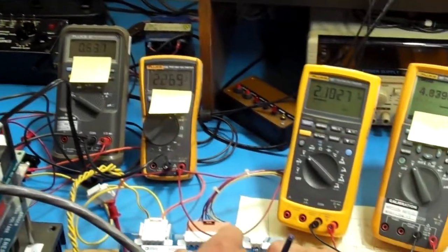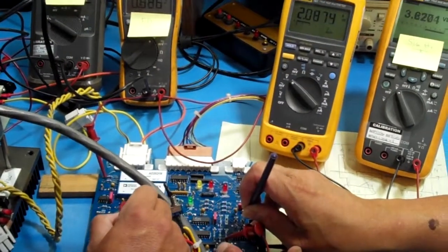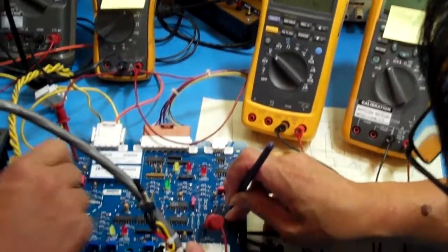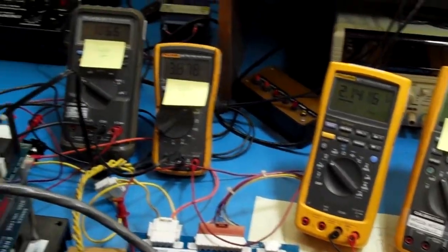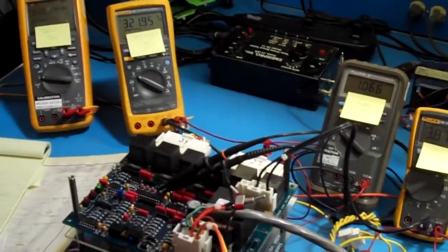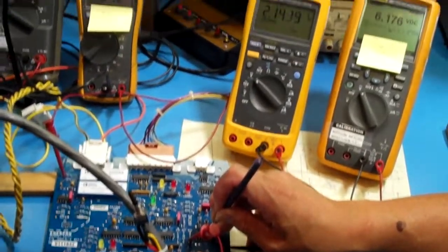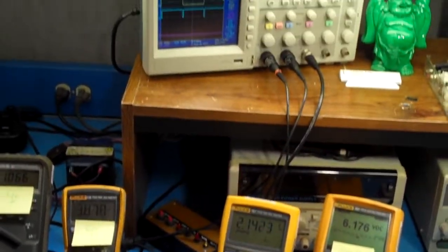The only way for me to clear it is to bring that threshold just above 2 volts. Pin 3, and now I'm cleared again. So that's for the trip, and now I can command with the current and the voltage anywhere on the value of my voltage, depending on whether I use current or voltage.